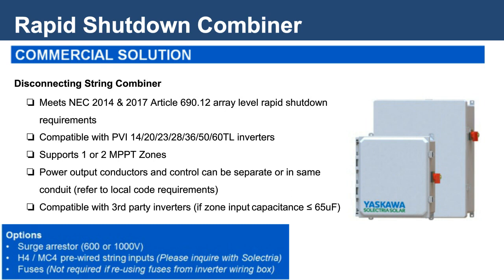This product is also compatible with third-party inverters, so long as the zone input capacitance of that inverter is below 65 microfarads. If you have any questions about the technical requirements of this product or its application with other non-Solectria inverters, I encourage you to contact the Solectria staff. This product can be provided with a number of options as well. Surge arresters to eliminate strike potential on the DC side of your array, as well as H4 or MC4 pre-wired whips, if this would be a benefit to your string wiring on the array.